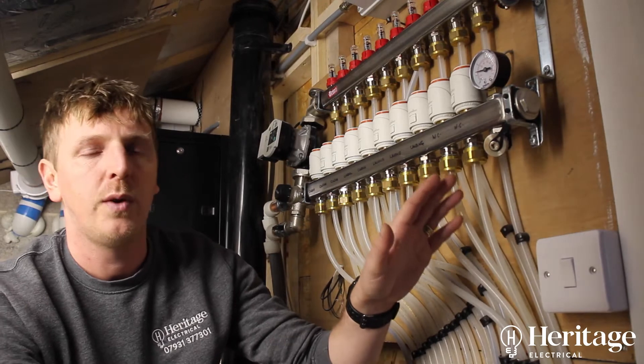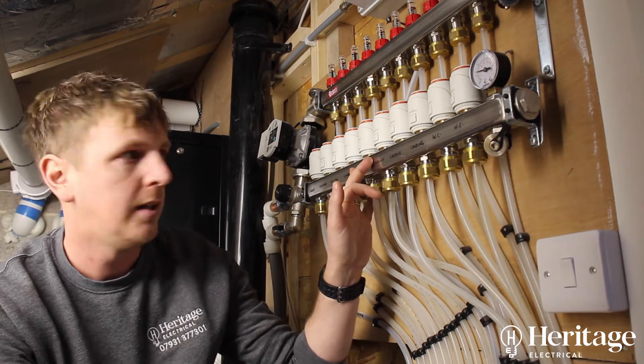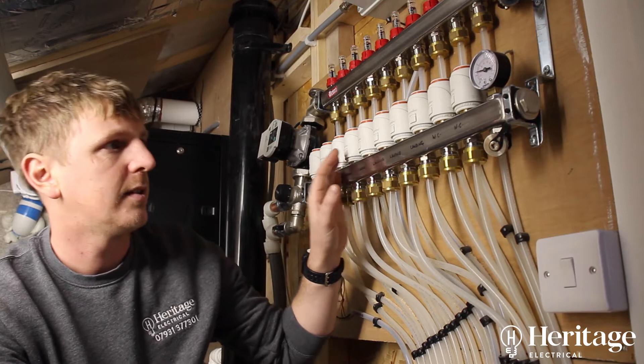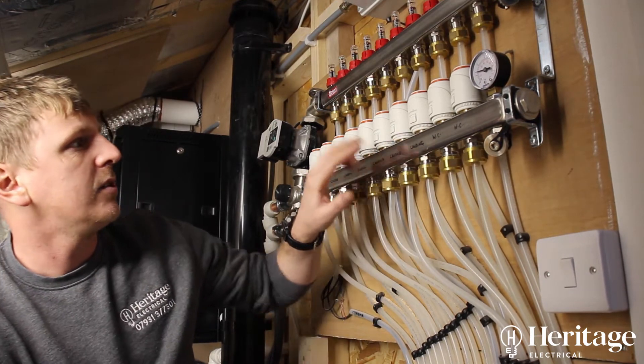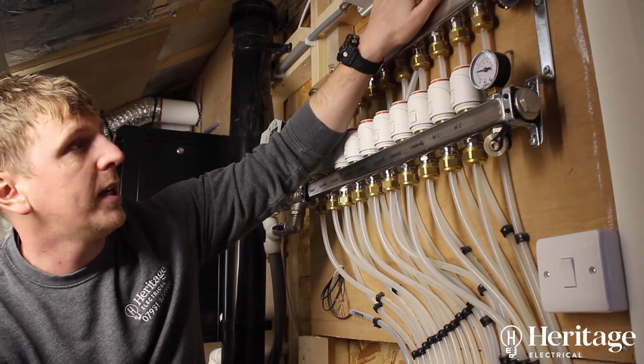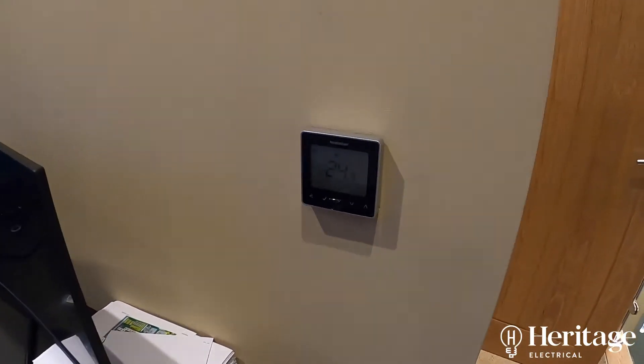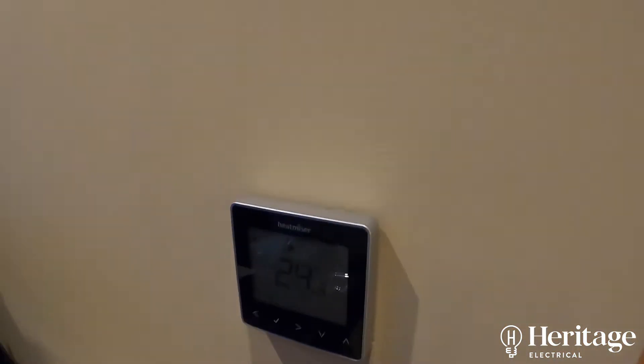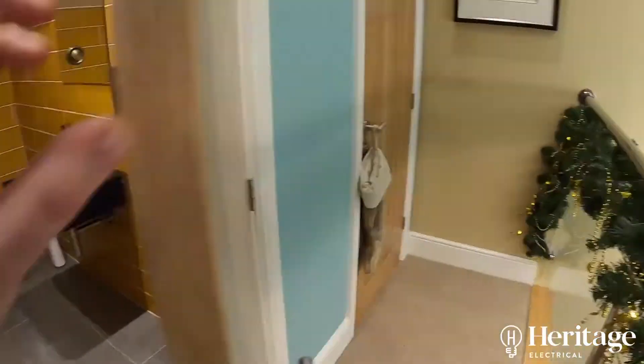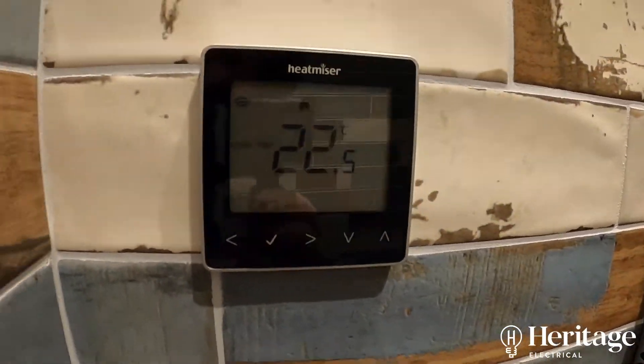Even though we've got a 10-way manifold, we're only controlling four circuits, so we've got ten actuators only controlling four circuits. The landing actuators are all wired into a joint box up here and then go out to the Heatmiser unit. One thermostat is controlling the four cinema room actuators, one thermostat is covering the three landing loops, and then two thermostats — one in each toilet — control the temperature in each toilet.